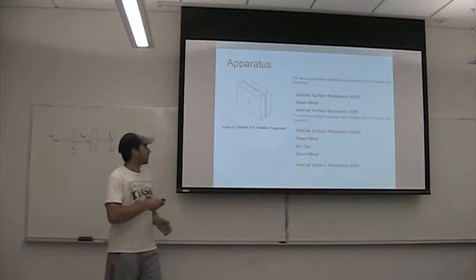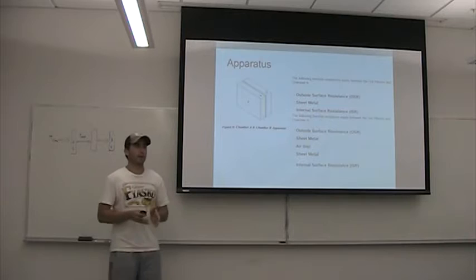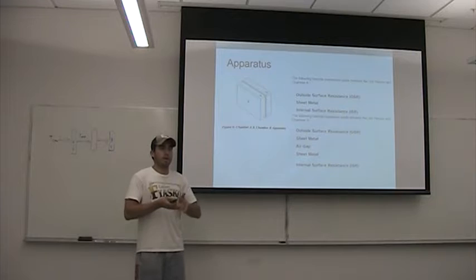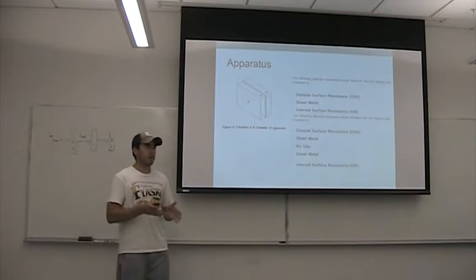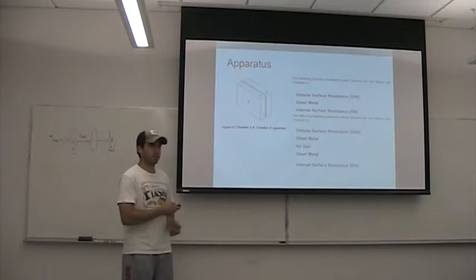With chamber B, it's a little different because you have your outside surface and your sheet metal. You also have an air gap, and then another sheet metal. The difference is the air gap. This air gap is an insulator when it's still and it isn't moving. It isn't convection, it's actually conduction. You see this in windows, double-sealed windows, and this helps to insulate and to make it more efficient.